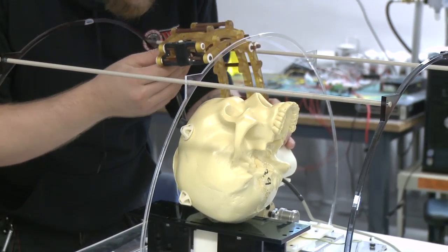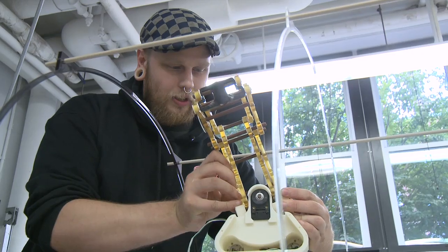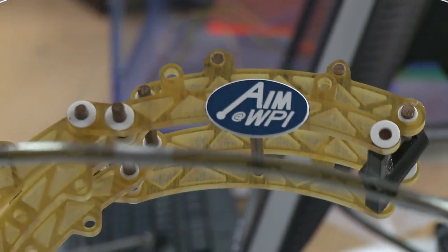What we're trying to do here is take the electrode and put it right into the brain. The robot that we built incorporates these sensors and actuators that we've been developing. This is an all-plastic robot, powered by ceramic motors using controllers that we've developed here in the lab, designed to give very low noise and high precision motion. This lets us move this manipulator to align the electrodes without interfering with the scanner at all.